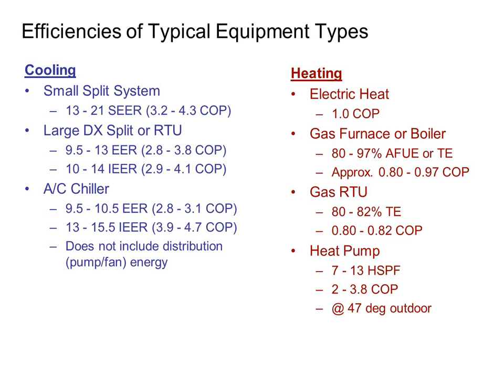Now, natural gas is very cheap in our market, so it may be the cheaper energy source to run your building in some cases, but it's not going to be the least energy using source. Rooftops are worse off than the furnace and boilers because hardly anyone has a condensing rooftop. I know there are some newer ones that we've worked with on our projects where we have condensing rooftops, but for the most part, 82% efficient is kind of your max best on a rooftop unit. And then you have heat pumps.